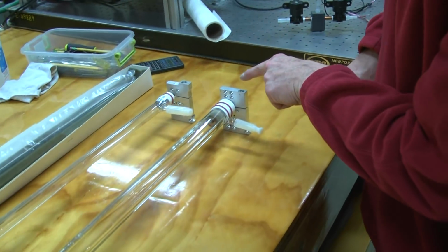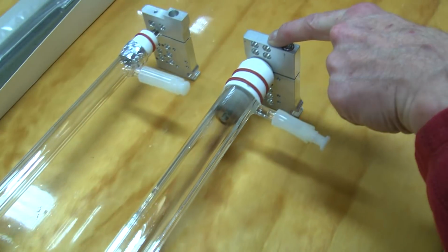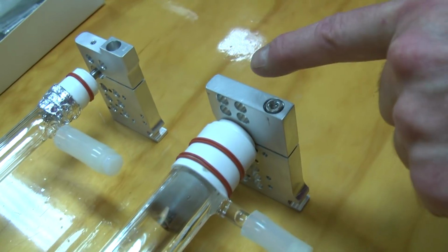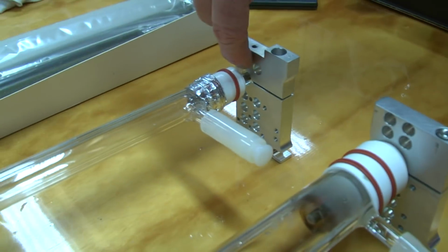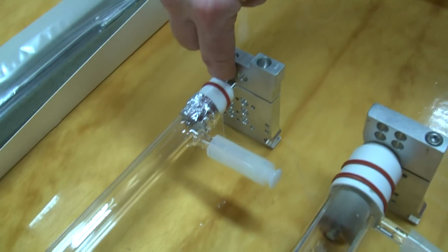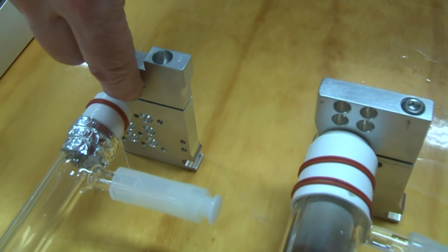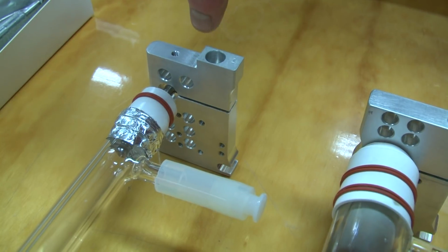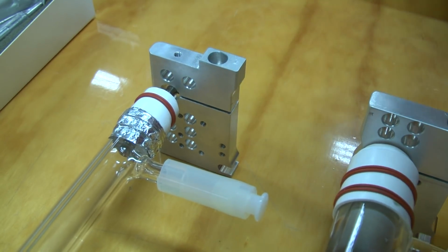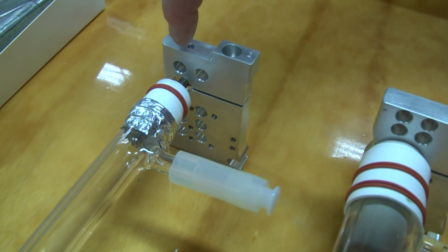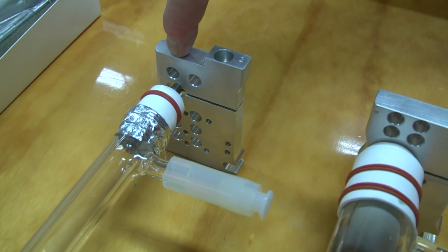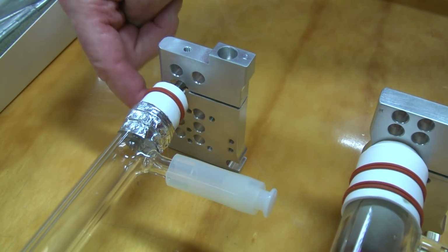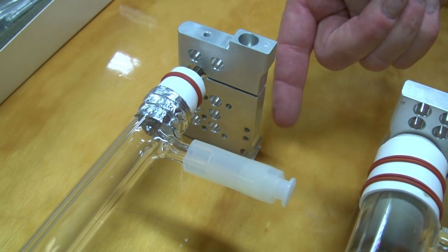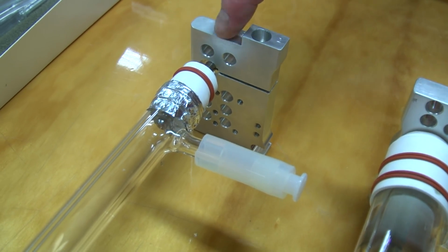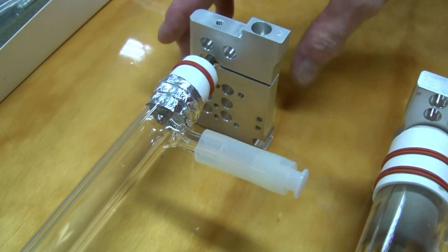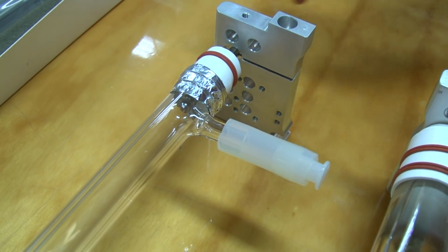If you look here too, you'll see this is how I support the flash lamp. These plates of aluminum are bored out, better probably seen over here, are bored out to slip fit the posts that come out of the lamp. And then a slice is made here to allow you to clamp this down and produce a very nice squeeze of the end post. Gives you very good thermal and electrical contact. And because of this very large aluminum, highly conductive plate with a lot of cooling holes in it, it gives you the ability to keep the electrode cool as well as support the electrode in a certain position.